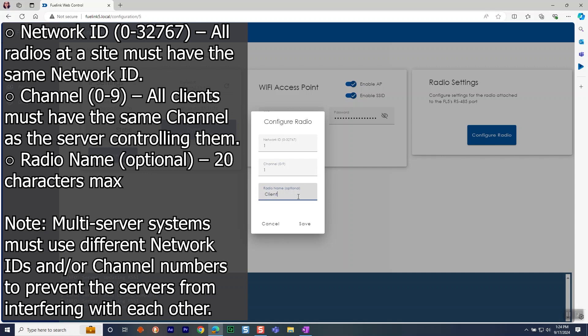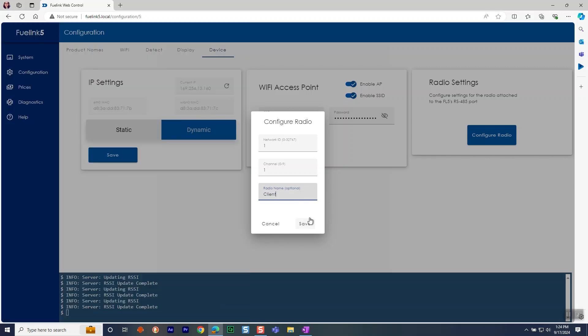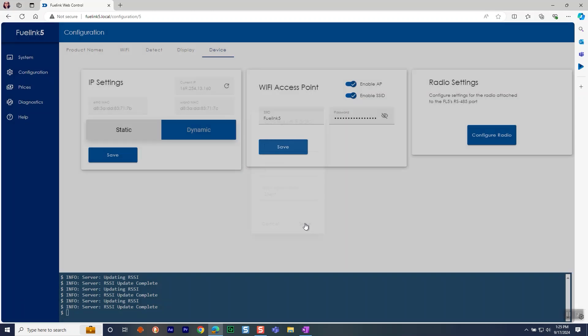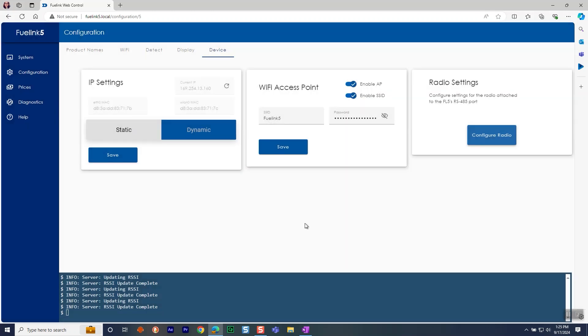The radio name is optional, but has a 20-character max. Make note that multi-server systems must use different network IDs and/or channel numbers to prevent the servers from interfering with each other. Once you have set the network and the channel, click Save to finish the configuration.